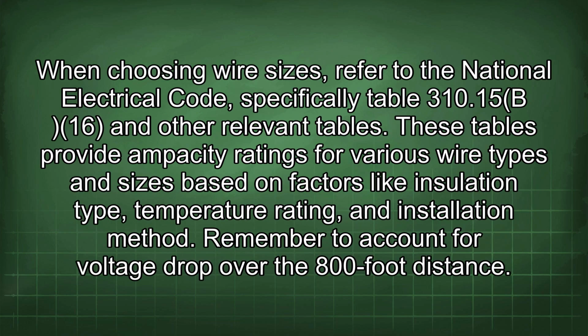When choosing wire sizes, refer to the National Electrical Code, specifically Table 310.15(B)(16) and other relevant tables. These tables provide ampacity ratings for various wire types and sizes based on factors like insulation type, temperature rating, and installation method. Remember to account for voltage drop over the 800-foot distance.